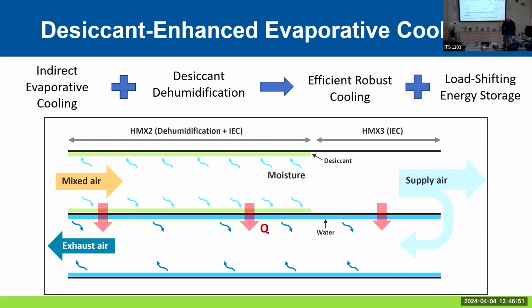In real time, like during a peak load event, there's a trade-off between efficiency—especially the efficiency benefits—and dehumidification. Is it a direct relationship, or am I oversimplifying? It gets somewhat complicated because of the desiccant, at least in this system.